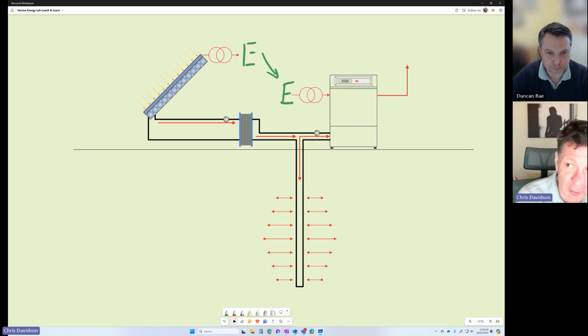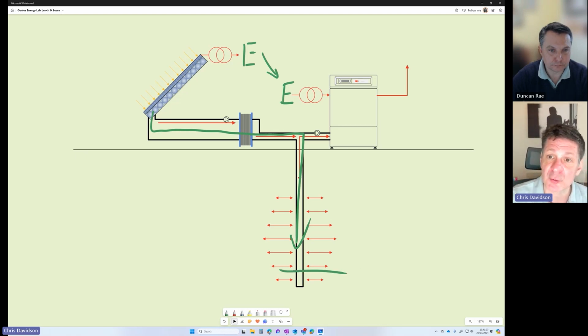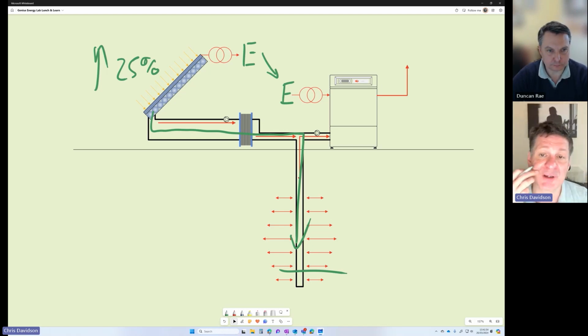More interesting though is if we've got thermal elements to that photovoltaic array - drawn here as a PVT, it could be a separate photovoltaic and thermal array alongside, or a combined hybrid PVT panel. What we're doing is taking solar thermal energy and injecting it into the ground loop, recharging that ground loop battery, putting heat back in. That can mean we need less borehole overall, but it certainly increases the efficiency of that ground source system - a real win-win. It goes further, because in cooling that PV panel, taking heat away from the back of it, we also increase electrical generation. In our trials and working systems, we're increasing electrical generation by about 25%. It goes further again - we're also increasing the longevity of those PV panels because of that cooling effect. So it's a lovely hybrid giving benefits in all regards.